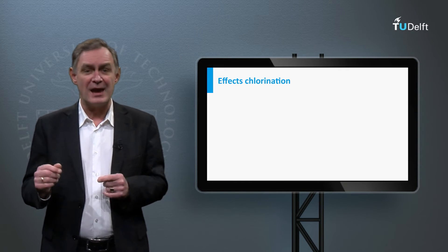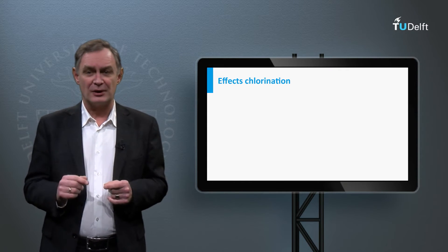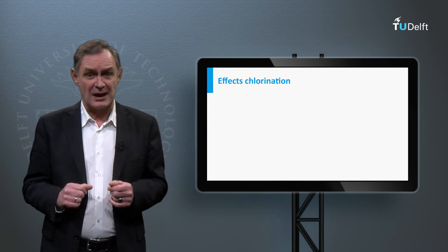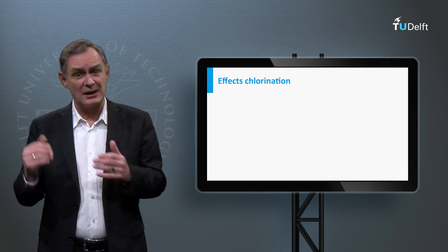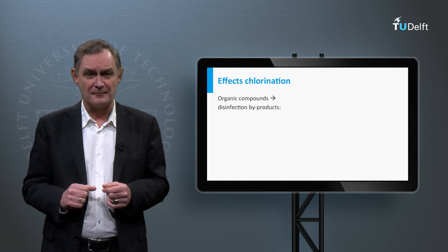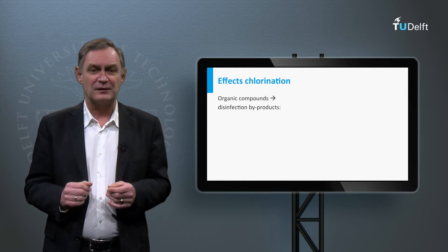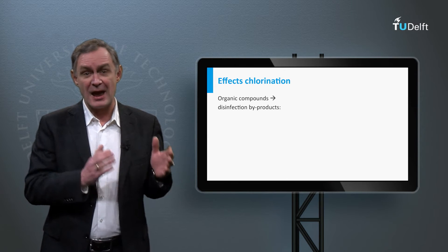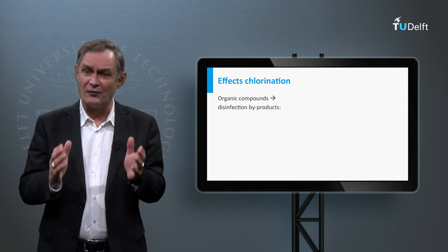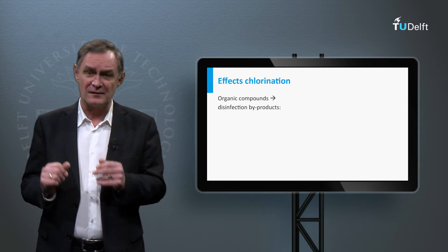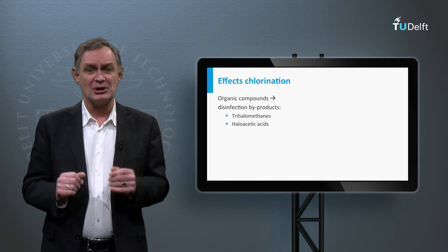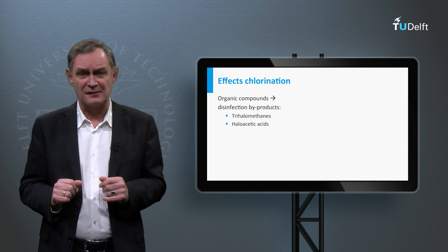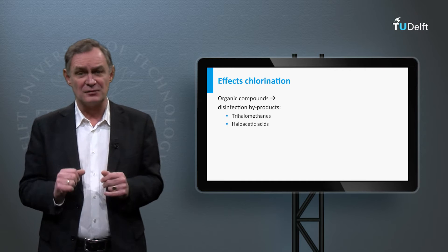All three chlorine components act as a disinfectant, but hypochlorous acid has better disinfection properties compared to hypochlorite. When chlorine is added to the water, it doesn't only disinfect microorganisms – it also reacts with organic compounds. This can result in the decrease of free available chlorine and the formation of harmful disinfection by-products such as trihalomethanes and haloacetic acids, which are carcinogenic.